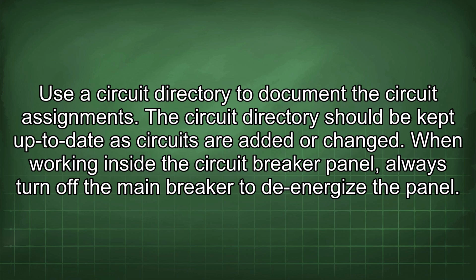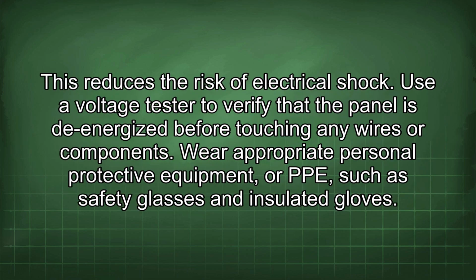When working inside the circuit breaker panel, always turn off the main breaker to de-energize the panel. This reduces the risk of electrical shock. Use a voltage tester to verify that the panel is de-energized before touching any wires or components. Wear appropriate personal protective equipment, or PPE, such as safety glasses and insulated gloves.